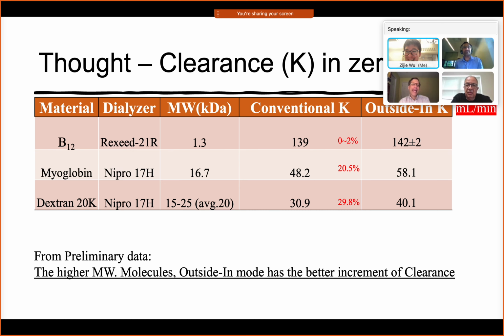Like I say, it is a nice way often to demonstrate that this really is the explanation, because with any of the other phenomena, fouling or something like that, why would switching the direction of the flow make any difference at all? Well, it shouldn't.